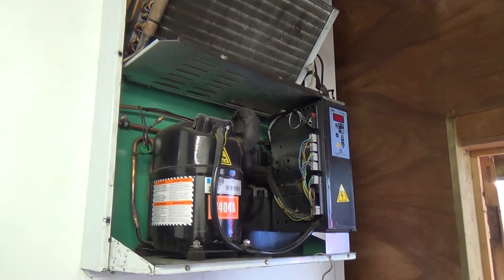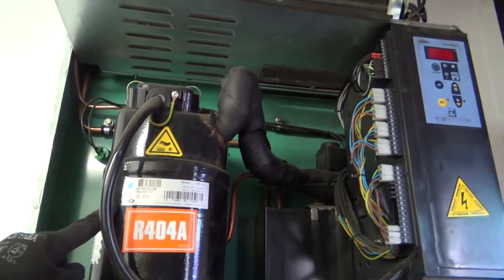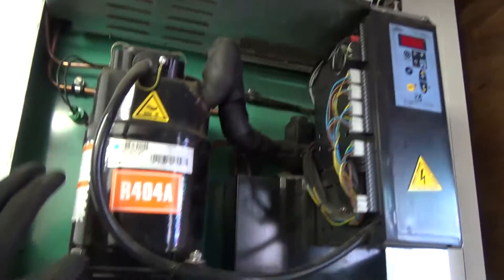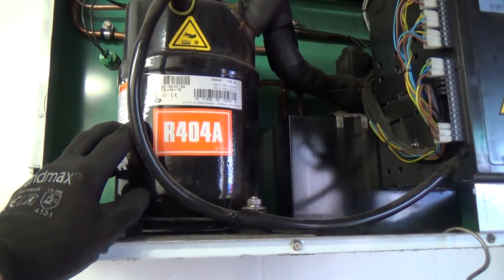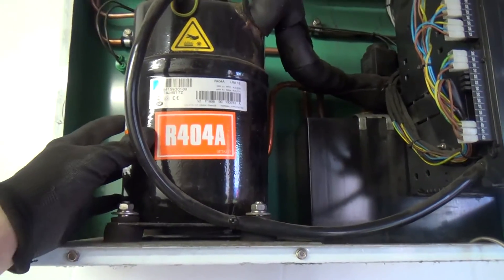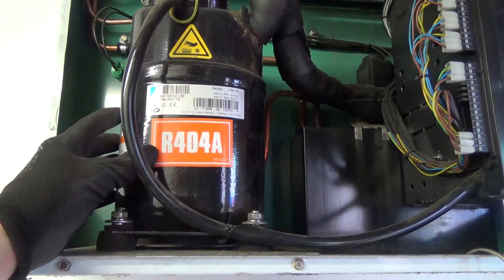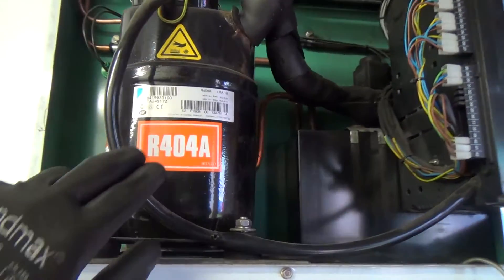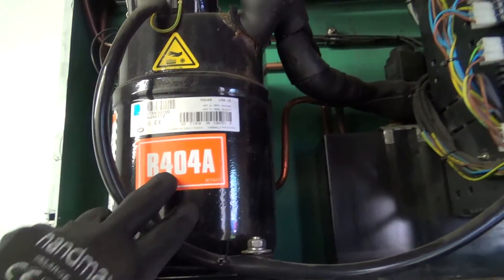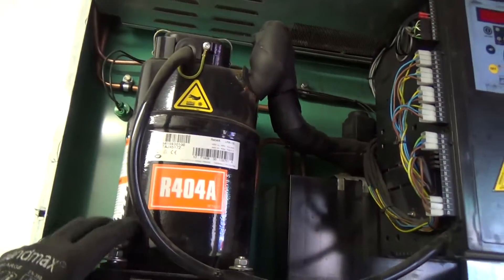Right, the job we've got today is to change this compressor. The customer's bought a second-hand cold room. It's a bit of a tight fit in here. And this is three phase and he's only got single phase on site. And he's not got the budget at the moment to put a new system in. So the cheapest option we've come up with is changing the three phase compressor for a single phase one and doing a bit of rewiring in the box to make it run. So that's the job for the day.